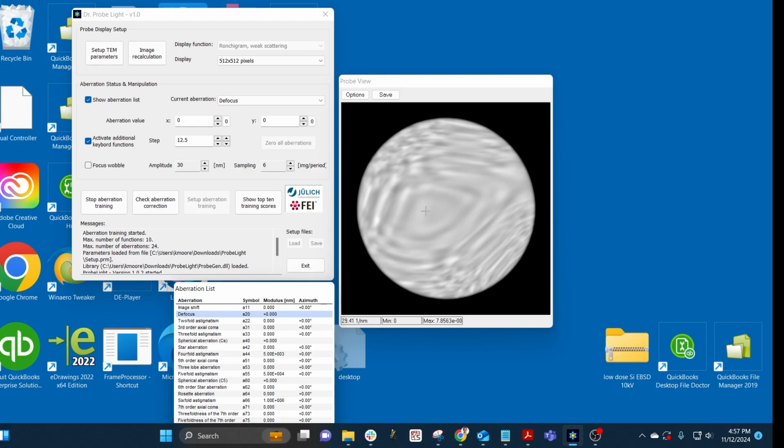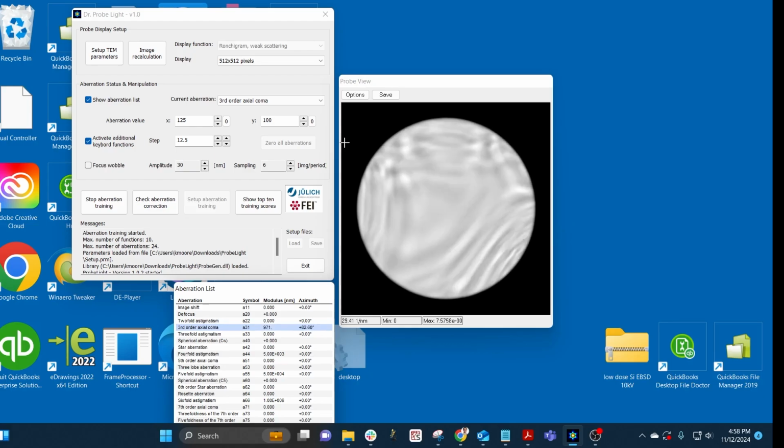The principle we're going to follow is that if you make it bigger, it's good, and if it rotates, you switch from your X stigmator to your Y stigmator, or vice versa. So I'm going to try on coma, and I'm adjusting it, and there's a little bit of rotation there, if you can see that. It's rotating, so I'll put it back to where it was initially and then switch to my other one. So this is getting bigger, which is good.